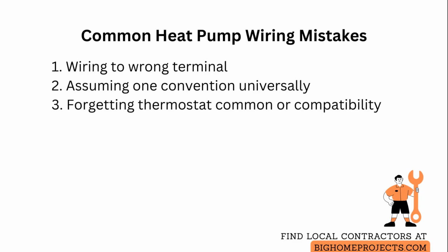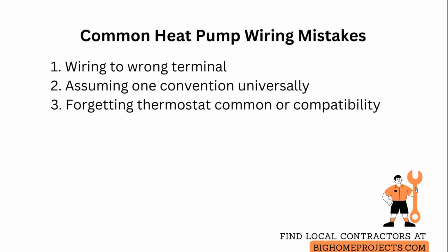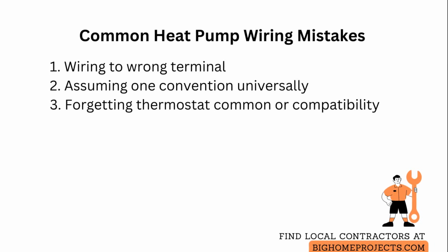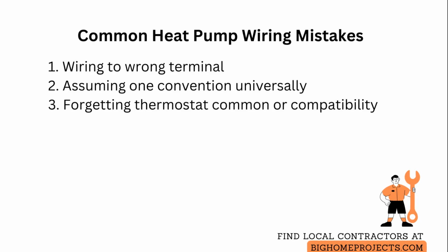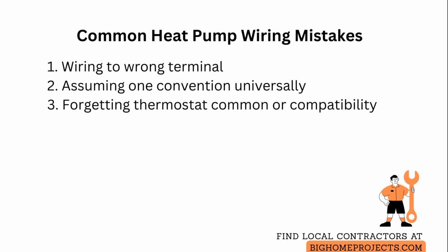Assuming one convention everywhere causes repeated callbacks, so verify the valve manufacturer and the outdoor unit wiring diagram before finalizing wiring. Forgetting the common or using a non-compatible thermostat can leave the valve without a complete circuit. So ensure the thermostat provides the correct voltage and returns to the transformer common, or use a separate relay if required.